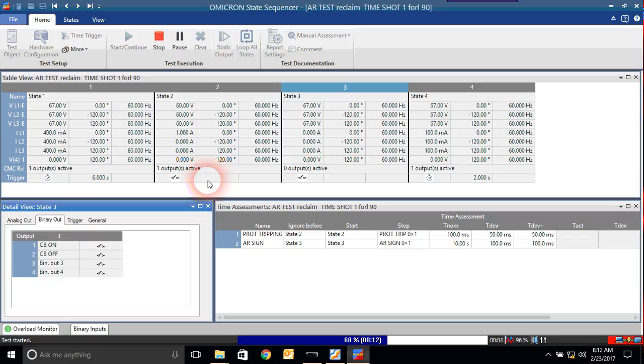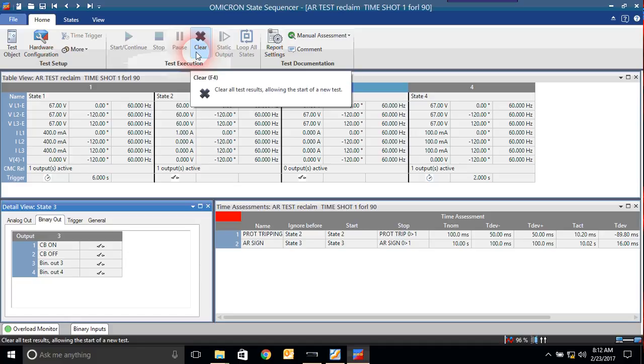Okay, still waiting. So he will count in seconds. If breaker still does not come to him, he will go to lockout. Okay, see, that's what I explained. I can simulate by too many ways. It's up to your understanding of this function and how to control this function, so you can simulate what you want. This is an easy simulation for this function. Select a point where you need to fail the sequence and knock it. Then you can get what you want.